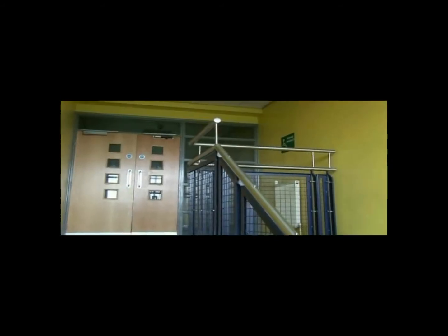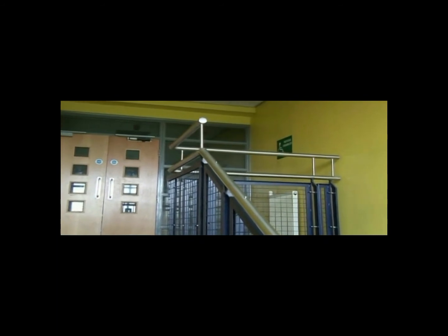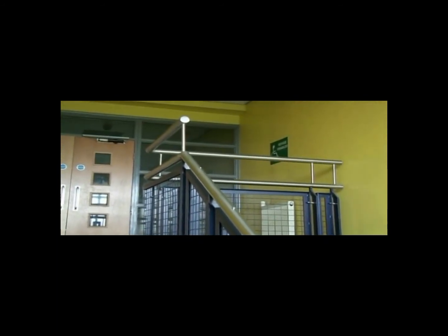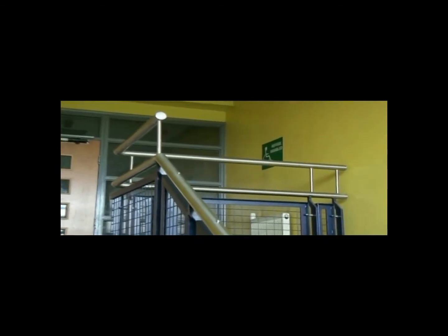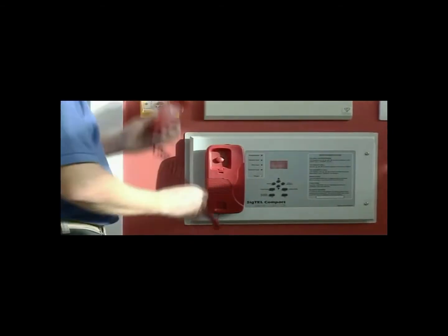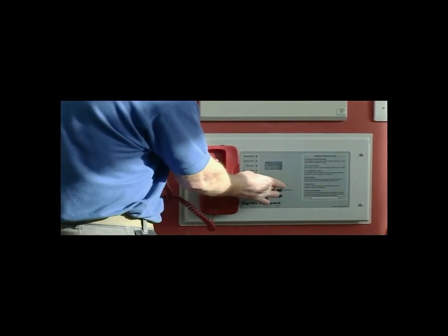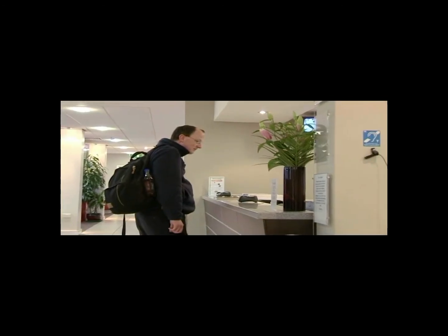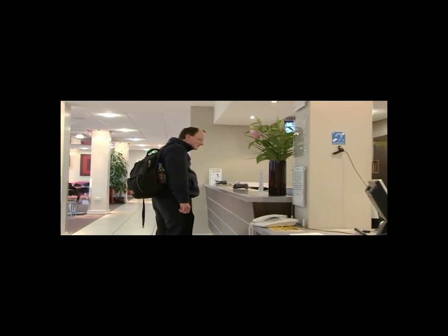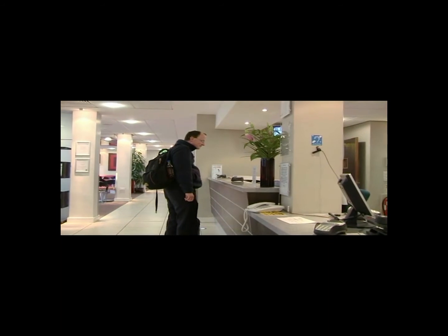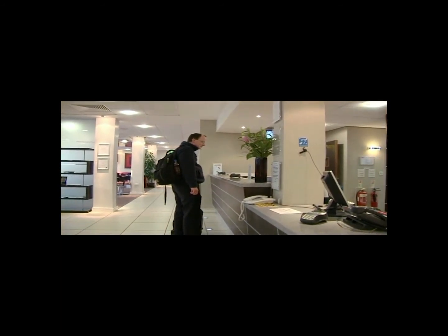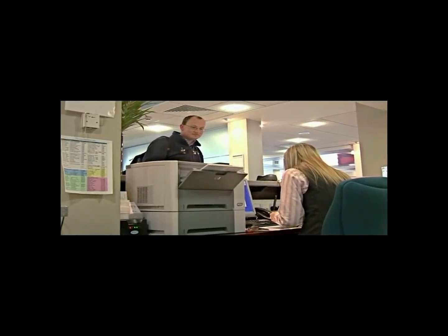Are refuges provided to assist in the evacuation of disabled persons clear of combustible materials, and are telephones and evacuation chairs in good working order? When considering people, it is important that you also think about how employees, visitors, or anyone else on site knows what to do and where to go in an emergency.